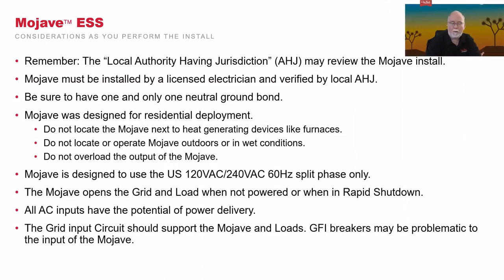So remember, when you install this, you're likely going to be under the umbrella of an authority having jurisdiction. This is going to be an inspector who's going to come in and look at it. So first of all, make sure that it's installed by a licensed electrician who can be verified by the local AHJ. Another important thing is make sure that it only has one neutral ground bond. If you have more than one, weird things happen. This even happens sometimes when they hook up generators. But if you see weird things happening, just make sure you have one neutral ground bond.